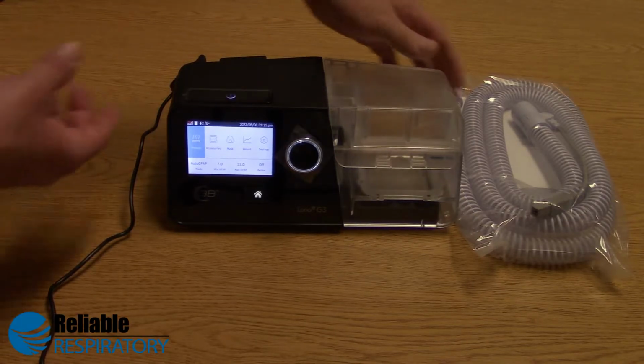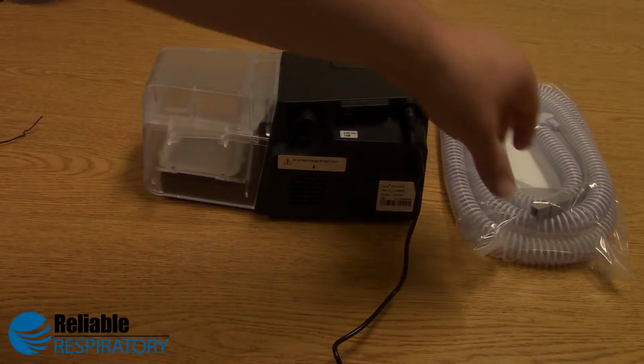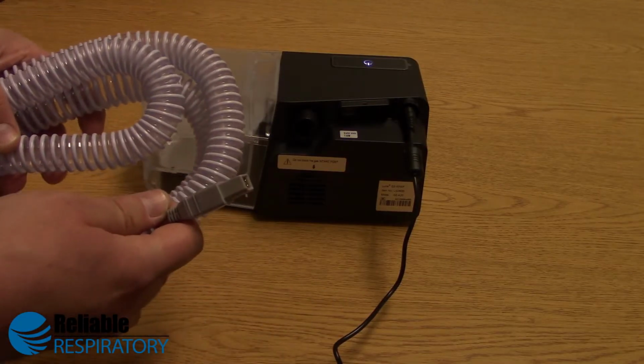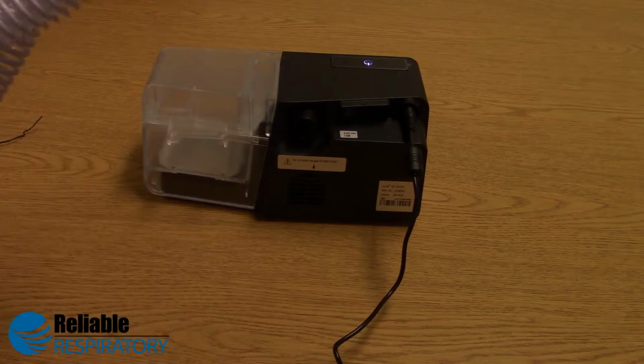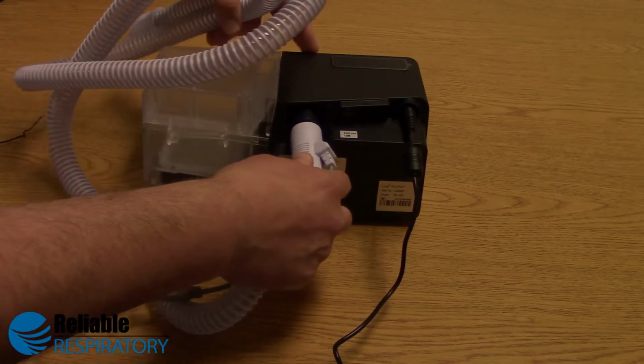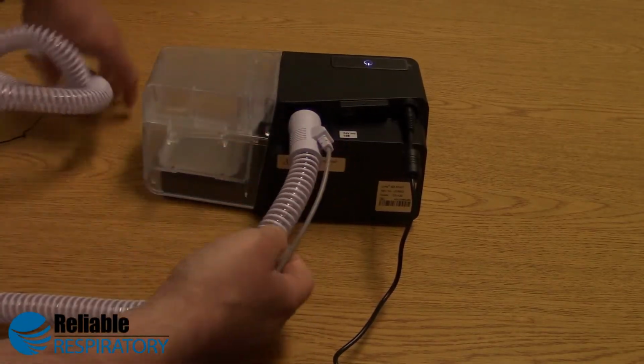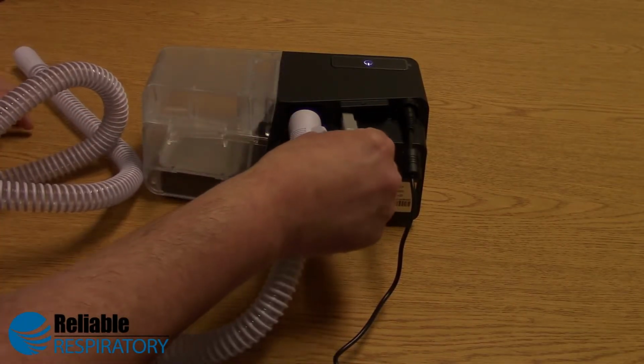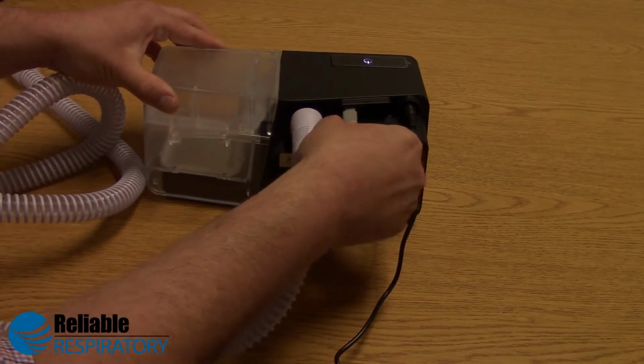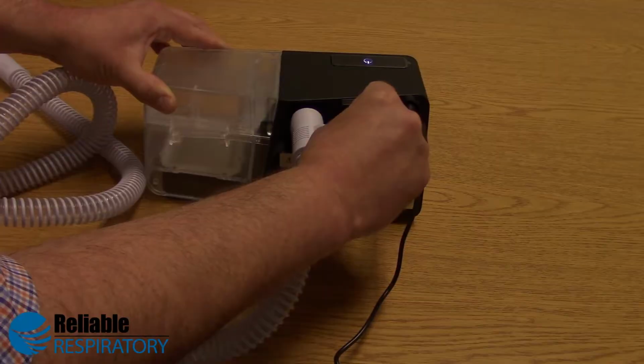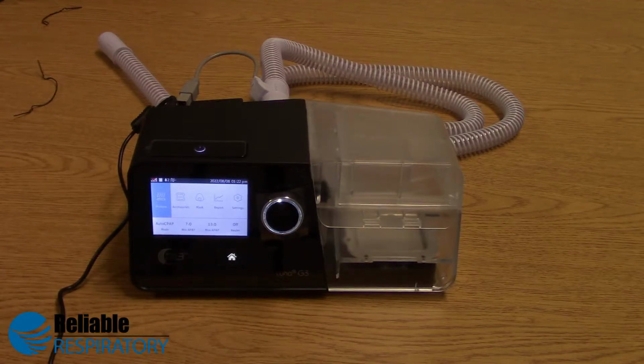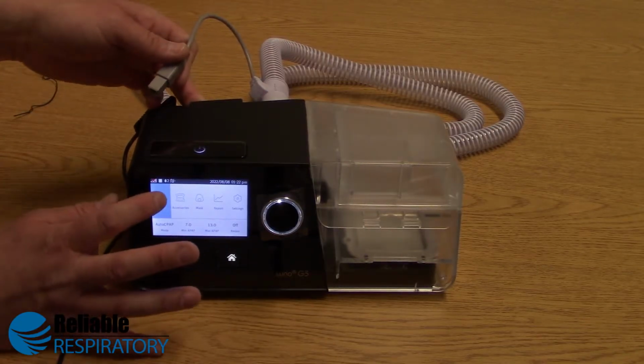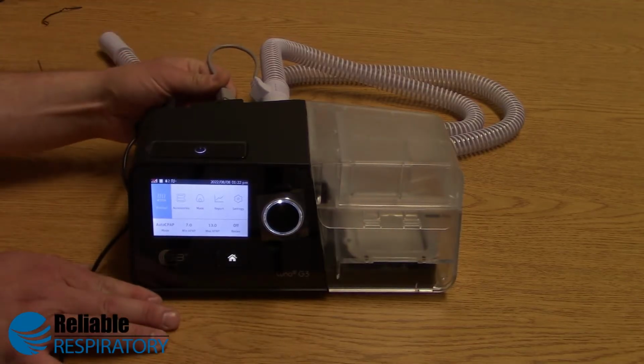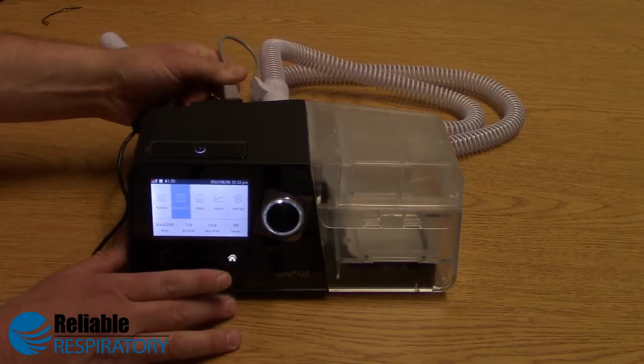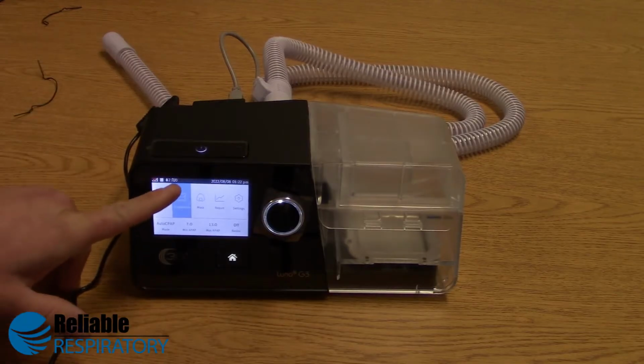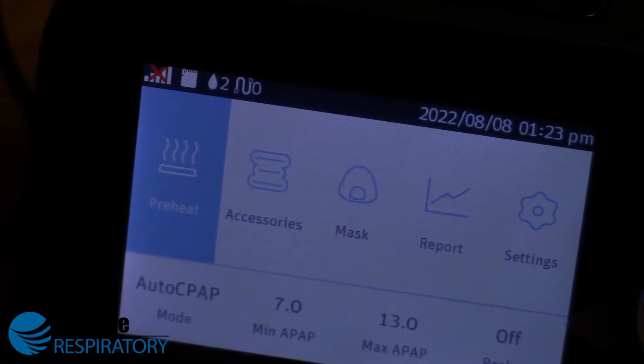Next, we're going to attach the heated tube, which is located on the back of the unit. The heated tubing comes with a wire probe connector that you'll actually plug into the back of the unit. So one portion of the hose, the actual large piece there, will attach like so. And the heat coil line will attach here. Luckily, it's set up in such a way that you cannot physically put it in incorrectly, and that will just slide right in. Without the heated wire dongle attached, you will see just an icon in this corner of a standard tube. Once I plug this in, you will actually see it change and a number shows up. And that number is the current heat setting for the heated hose.